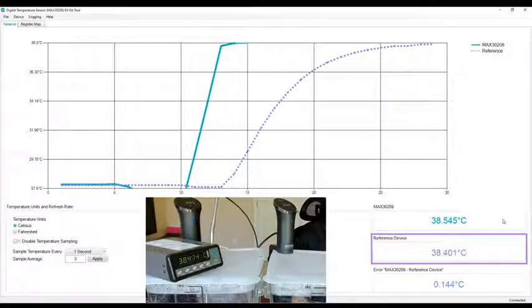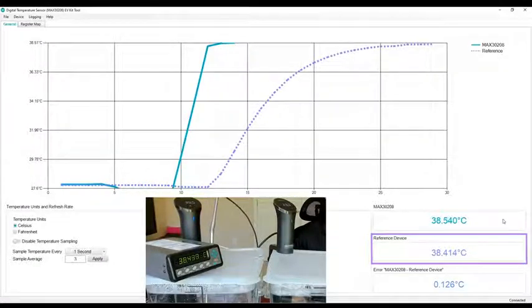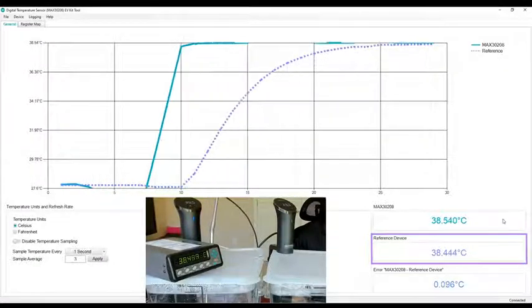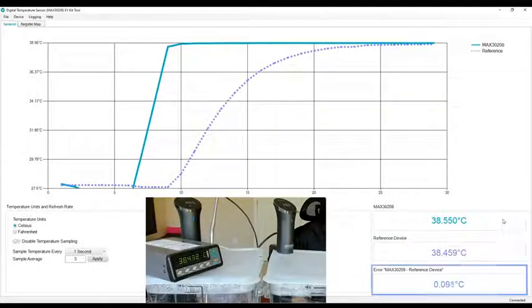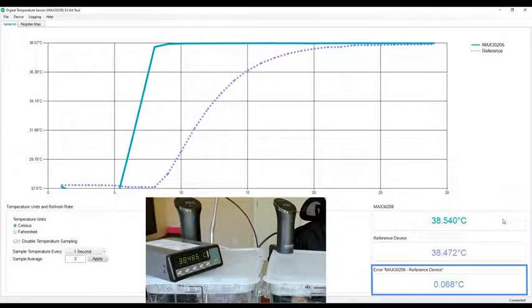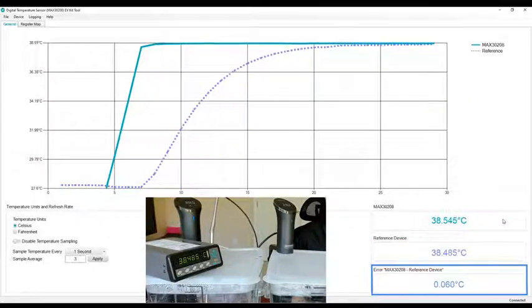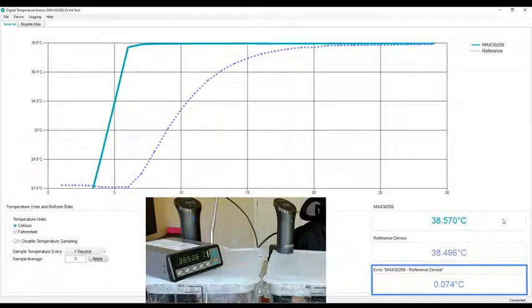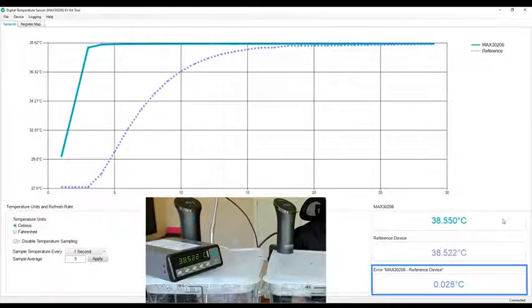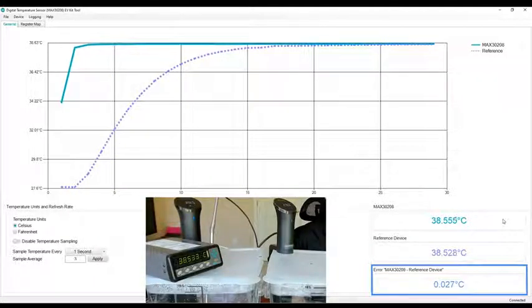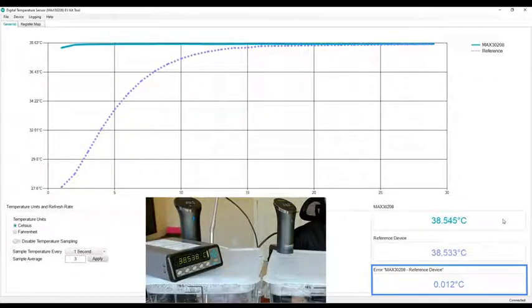You'll see that once the reference device has reached that temperature—once the whole thermometer is heated up—the accuracy is there at human body temperature and they're well within 0.1 degrees Celsius.